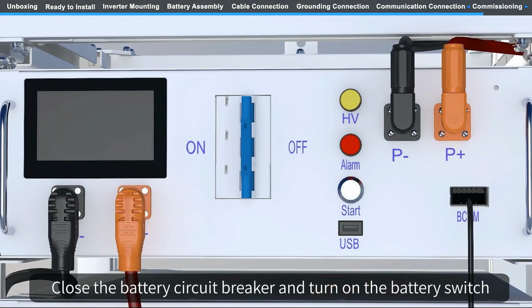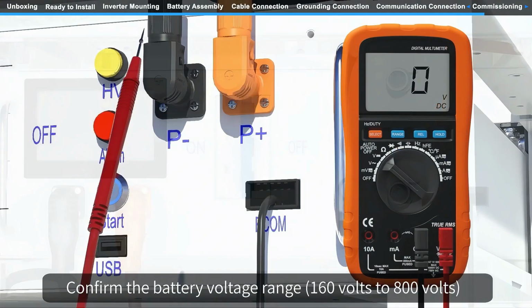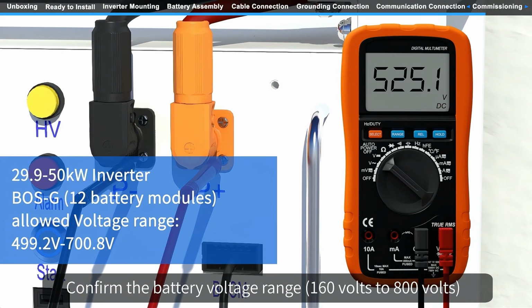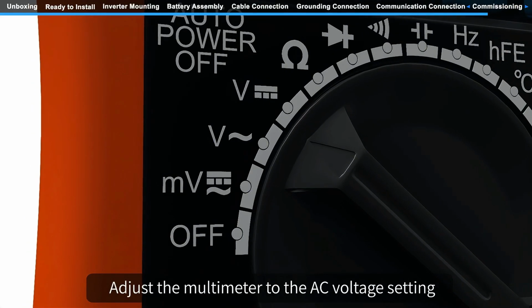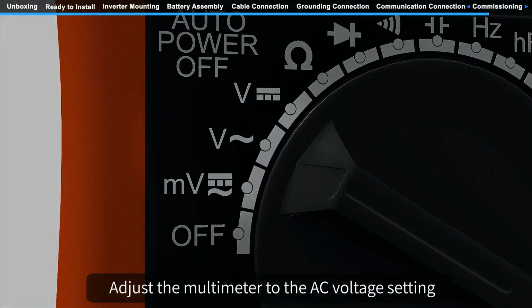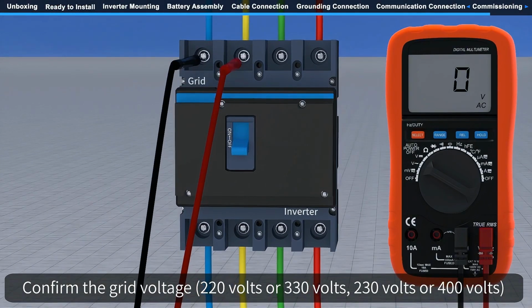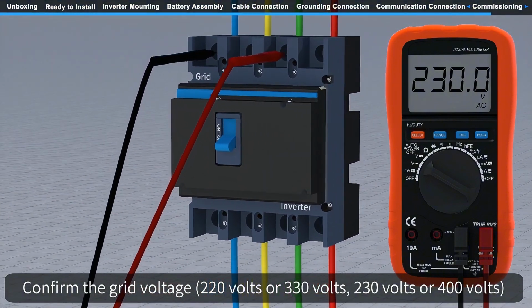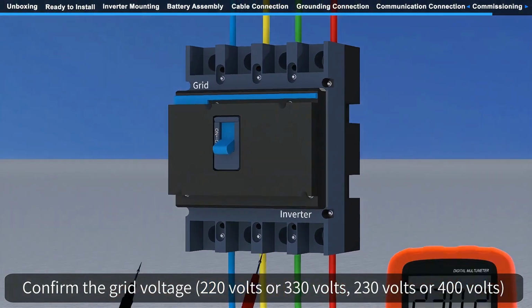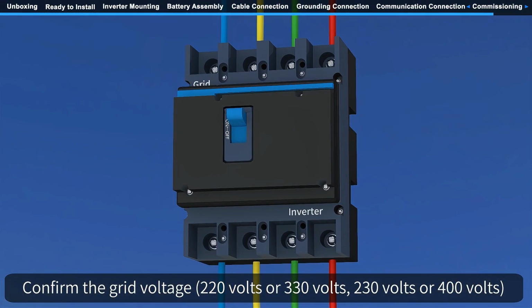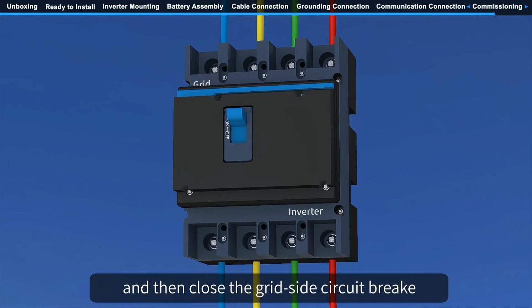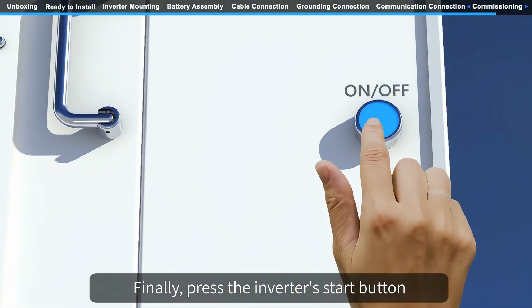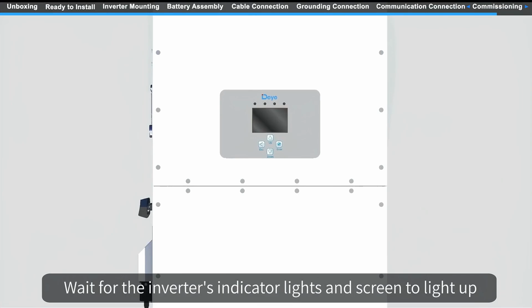Close the battery circuit breaker and turn on the battery switch. Confirm the battery voltage range 160 volts to 800 volts. Adjust the multimeter to the AC voltage setting. Confirm the grid voltage 220 volts or 330 volts, 230 volts or 400 volts, and then close the grid side circuit breaker. Finally, press the inverter's start button.